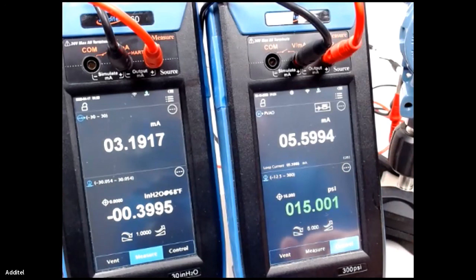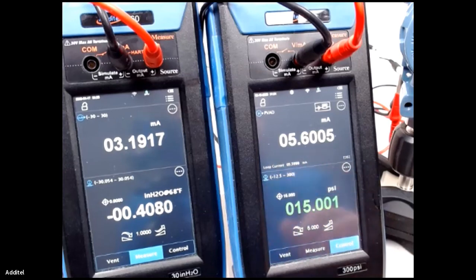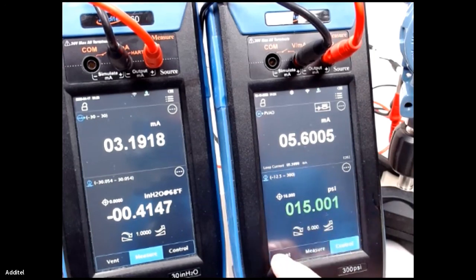This is kind of nice if you're down on the floor and you're the only guy, you don't have anyone in the control room, and you just want to step it up 20 psi at a time. You just hit the unit and walk into the control room and see, oh yeah, we're at 15 psi right now and we're stable, okay. So the other way to do that would be with the step function. I'm going to go ahead and vent this real quick here now.